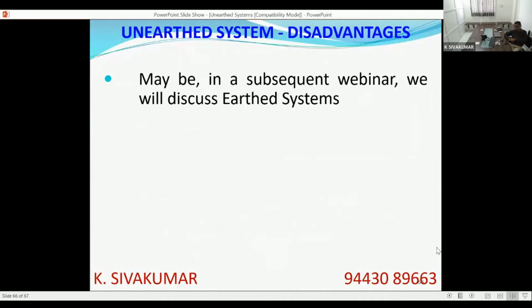So maybe in a subsequent seminar, we will slowly graduate to discussing the various advantages and disadvantages of each method of earthing, like the resistance earthing system. What are the advantages, disadvantages? The reactance earthing system, what are the advantages, disadvantages, and the analysis? Like we have done the analysis for the unearthed system now, we can also do the analysis for the resistance earthing system and the reactance earthing system, that is low reactance earthing and high reactance earthing, which is known as Petersen coil earthing or arc suppression coil earthing. Maybe a month from now we may conduct a second webinar, in which we will discuss the earthed systems more elaborately.